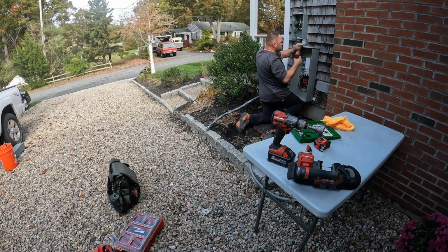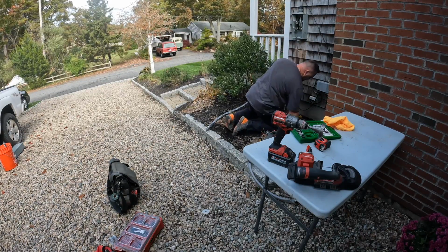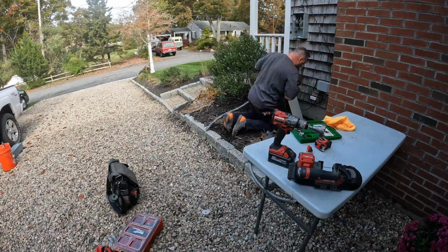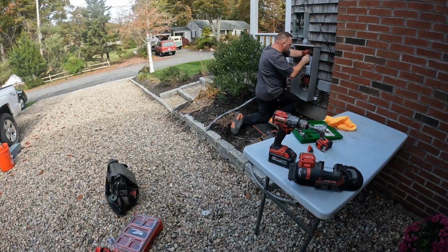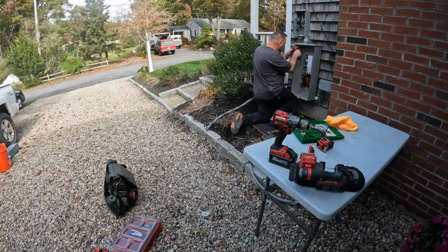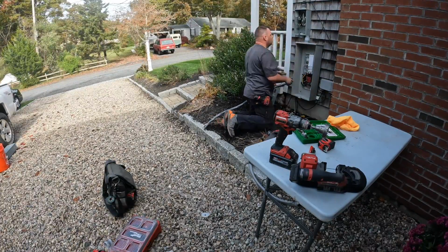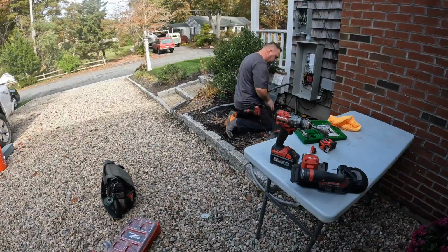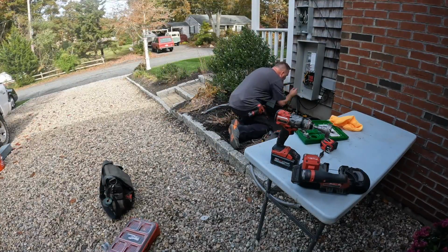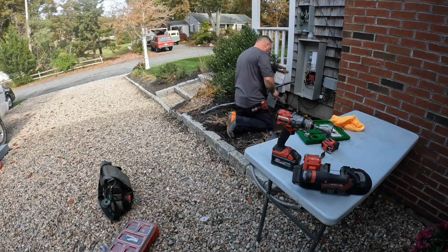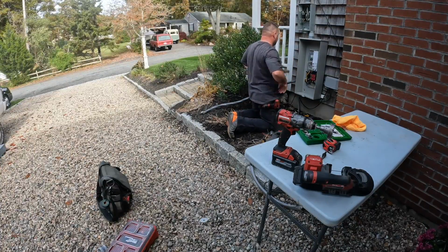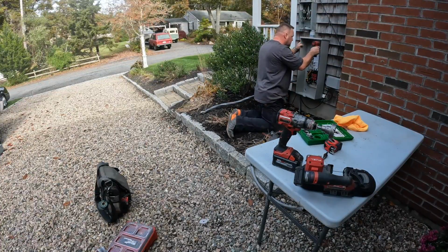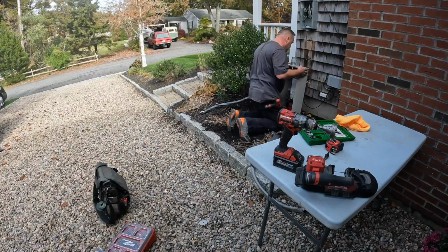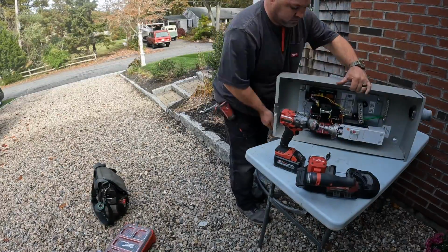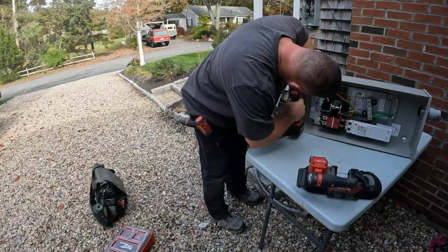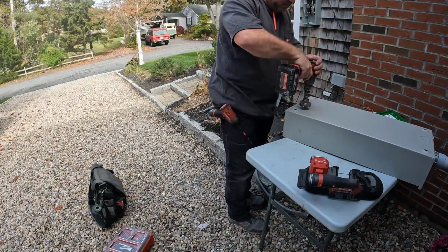So here I'm just doing a dry fit to try to figure out how I'm going to attach this automatic transfer switch, because it's not as easy as it looks. I've got to attach it to the bottom of the meter here. And then I also need to bring 2 cables in. One is a service riser cable that goes to the electrical panel down in the basement, and the other is the cable coming from the generator in the backyard. Both of these are going to go into the bottom section of this automatic transfer switch enclosure, but it takes me a little bit of time to figure out how that's going to happen.